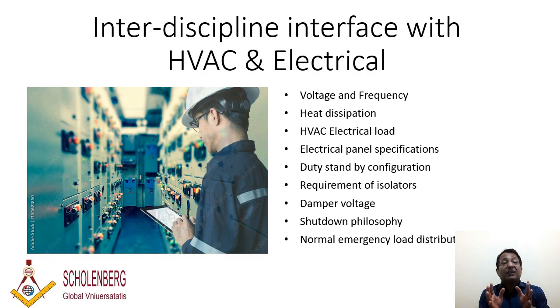Then you need to design the shutdown philosophy, because if something happens on the platform - say gas or fire is detected - how will your control panel or HVAC panel get closed? That kind of philosophy needs to be designed together with technical safety, electrical, instrument, and all major disciplines sitting together.